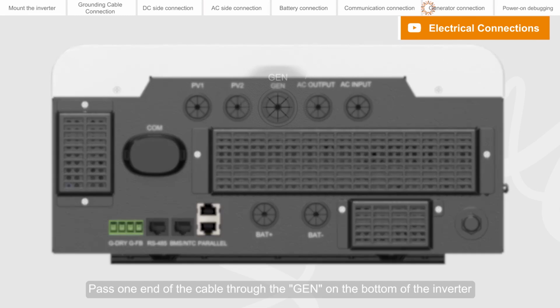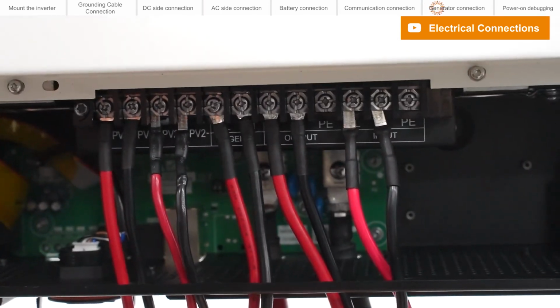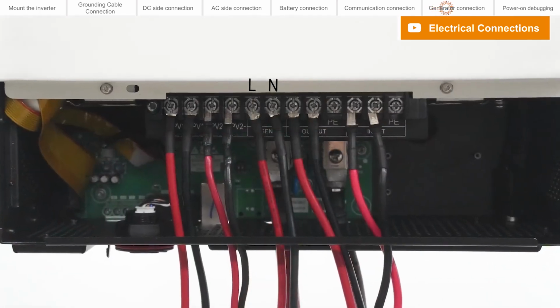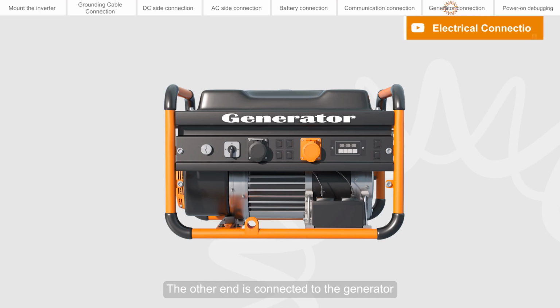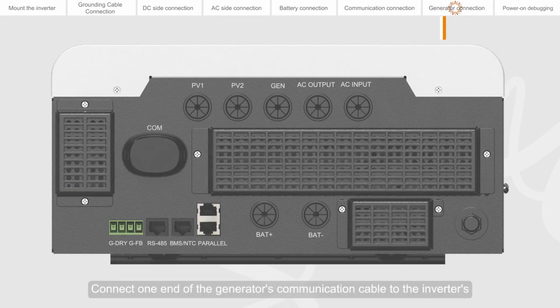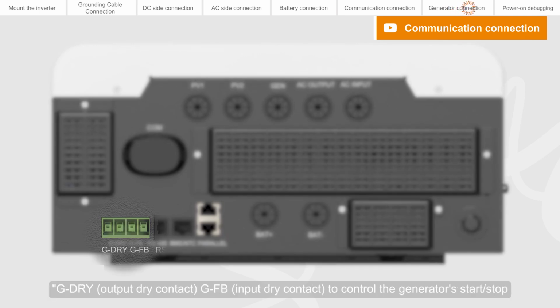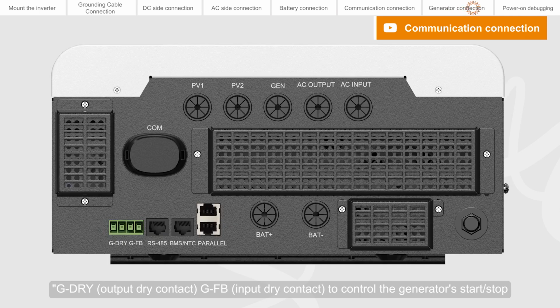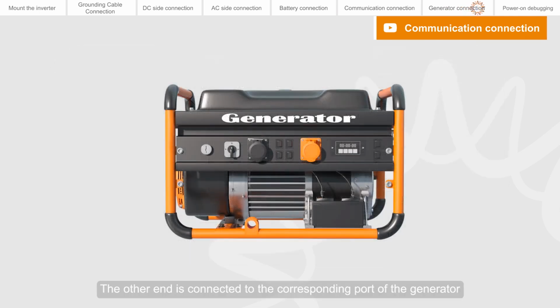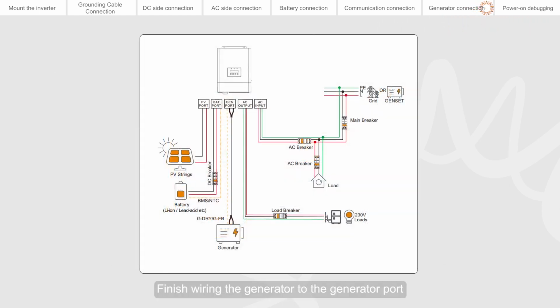Pass one end of the cable through the GEN hole on the bottom of the inverter. Connect to the GEN L and N corresponding ports. The other end is connected to the generator. Connect one end of the generator's communication cable to the inverter's G-dry, output dry contact, and GFB, input dry contact, to control the generator's start or stop. The other end is connected to the corresponding port of the generator. Finish wiring the generator to the generator port.